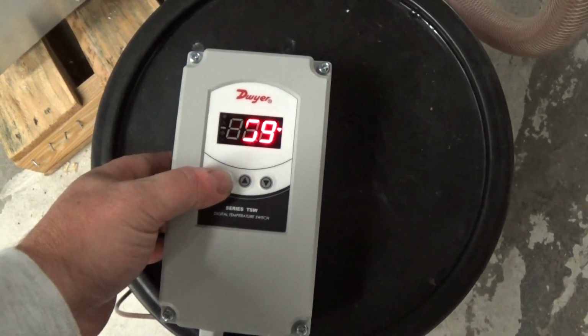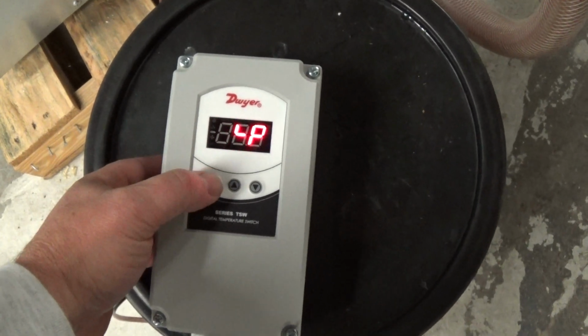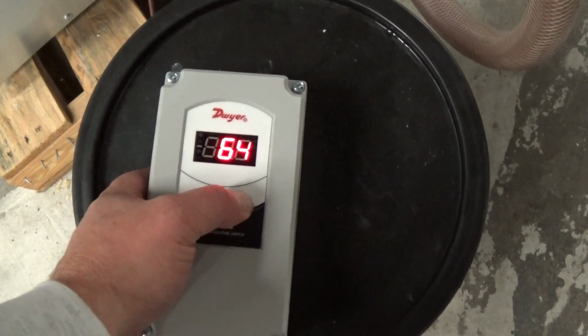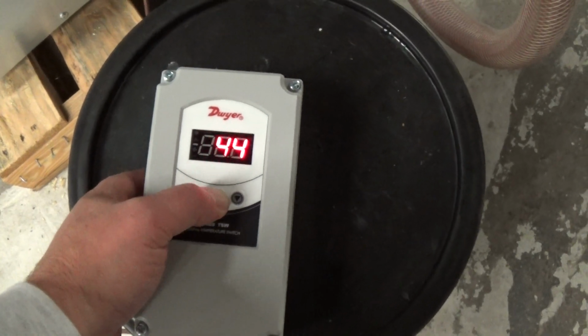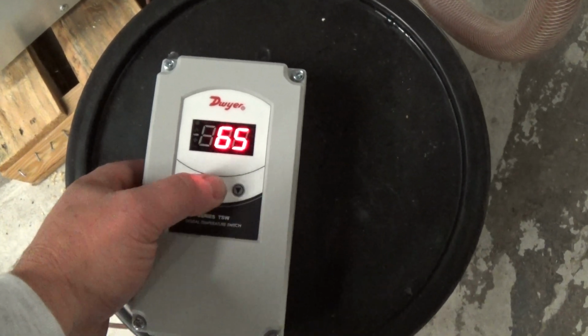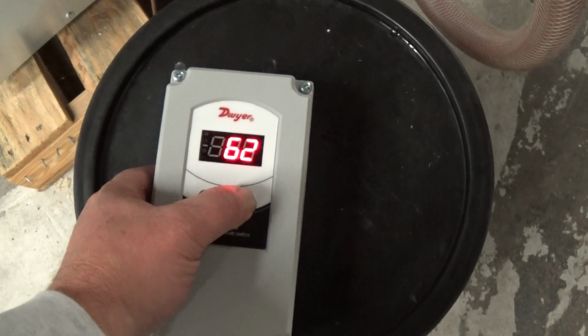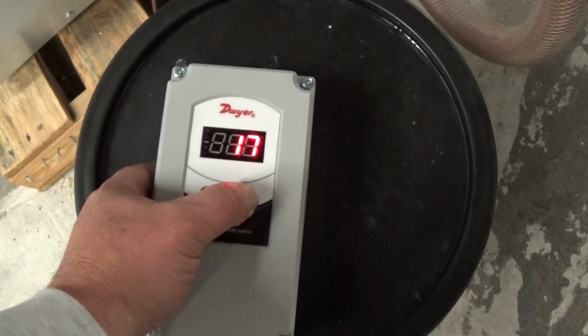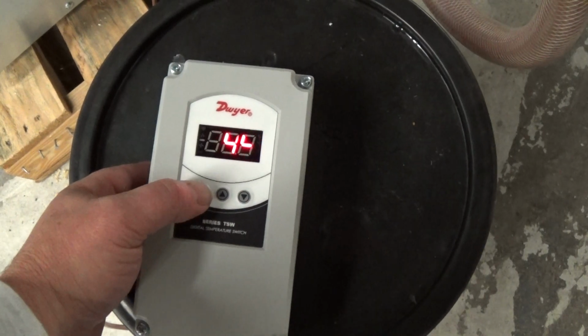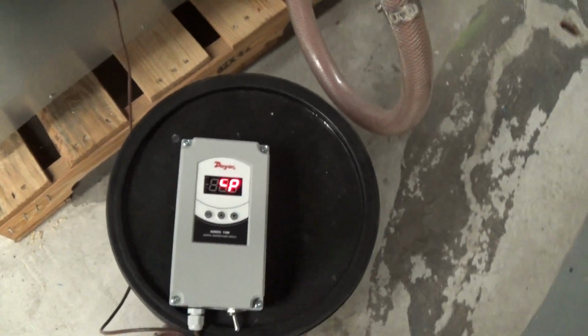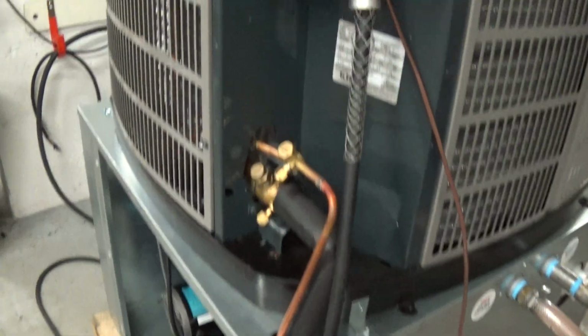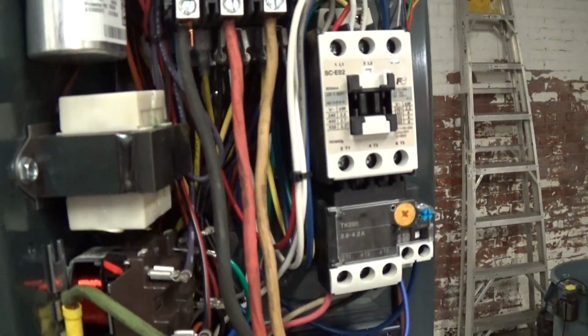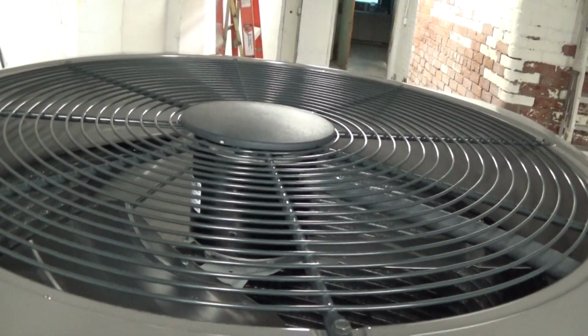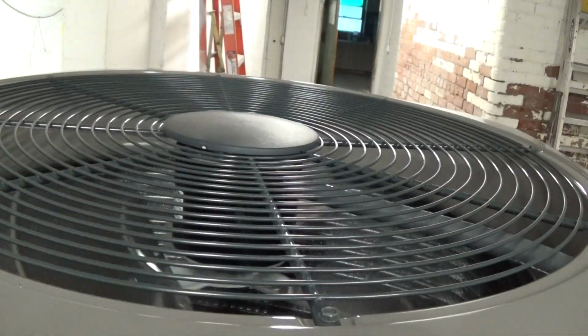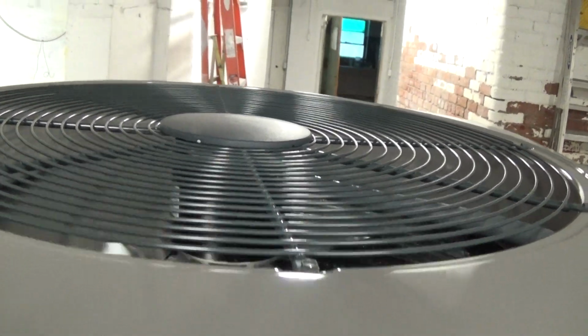You press set once, you press set again, then you press the down arrow or up, and it'll scroll through. You can see it goes right from 65 to 44. Bring it down to 44. Press set again, and you can hear the compressor just kicked on. And right now the fan is rotating very slow, or it's just starting to. Just starting out.